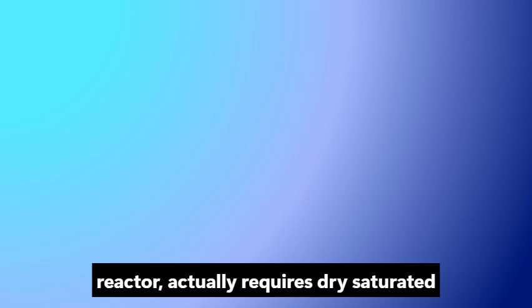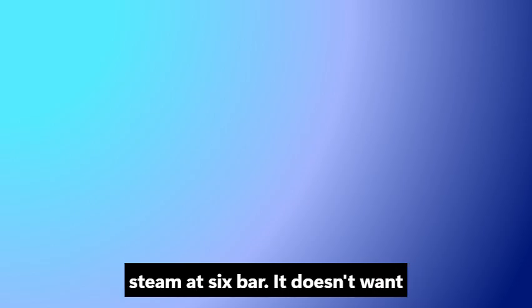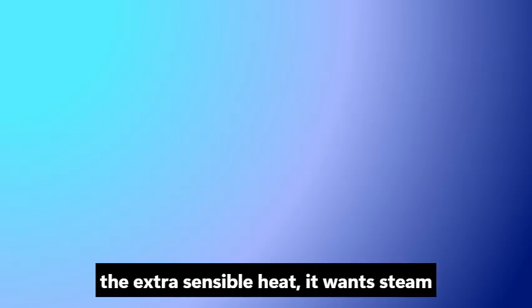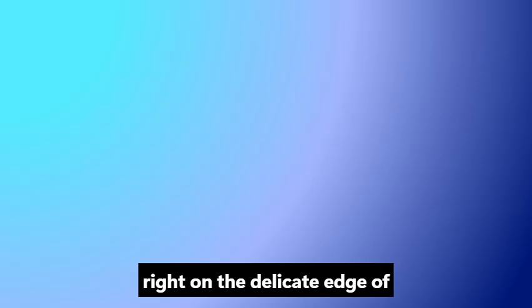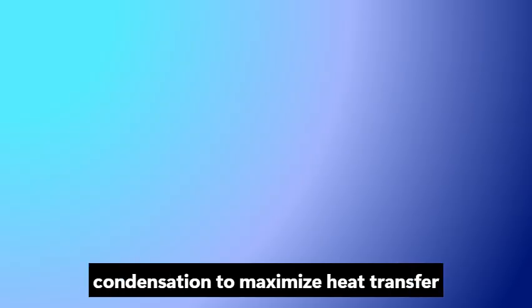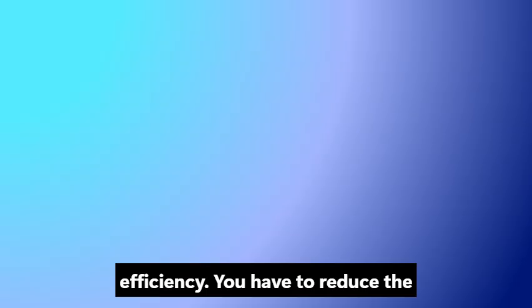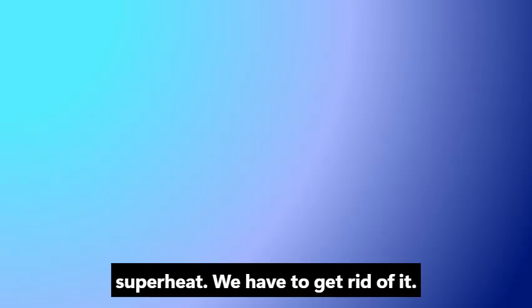Okay. However, the factory machinery downstream, maybe it's a massive heating jacket for a chemical reactor, actually requires dry, saturated steam at 6 bar. It doesn't want the extra sensible heat. It wants steam right on the delicate edge of condensation to maximize heat transfer efficiency. So you have to reduce the superheat. We have to get rid of it, yes.